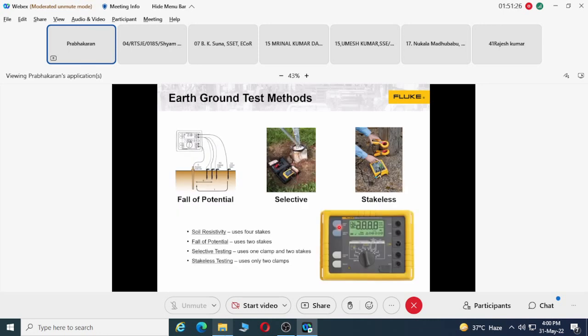and then get you the exact earth resistance of that system. These 4 methods are important because you will have different facilities, and in all places you may not be able to apply the same method. In a building you may not be able to use the stakes, there you may have to use the clamp. In the field you can use the stakes. But if the substation is completely concreted, then you may not be able to use this - that is the time you may have to use this kind of clamps.